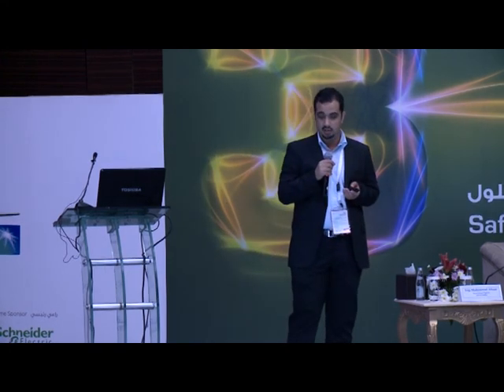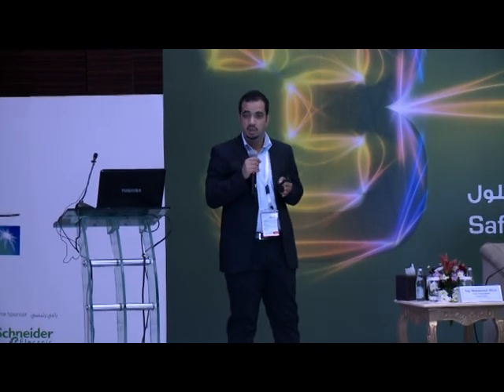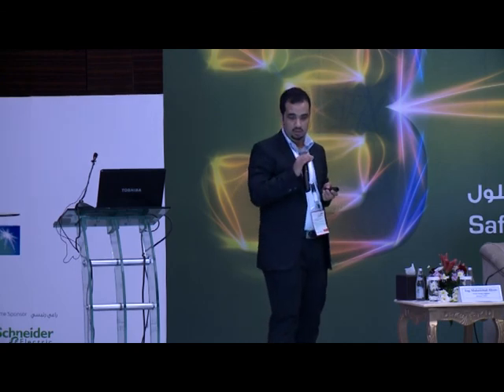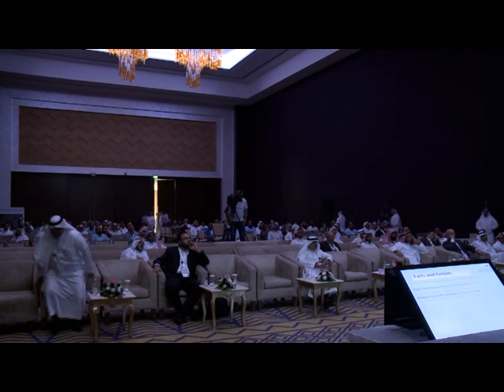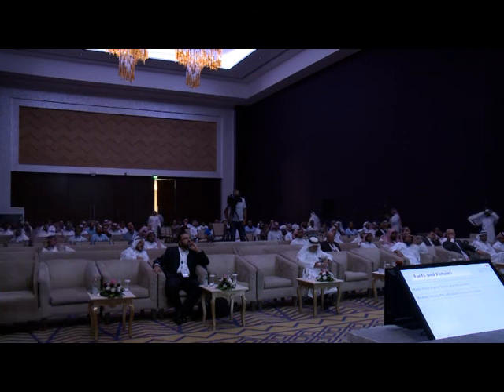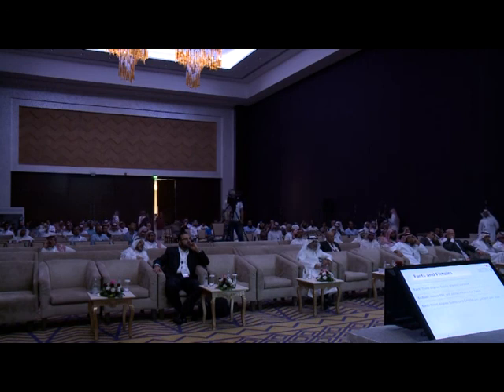The first fact is third-degree burns are not curable. The purpose of arc-rated PPE is to limit the hazard to the second degree only. Heavy PPE will protect from arc flash. That's not true. PPE will not protect from energy greater than 40 calories per centimeter squared, as the blast pressure will be the dominant factor in this case. Third-degree burns cost $4 million per patient per year only for treatment.